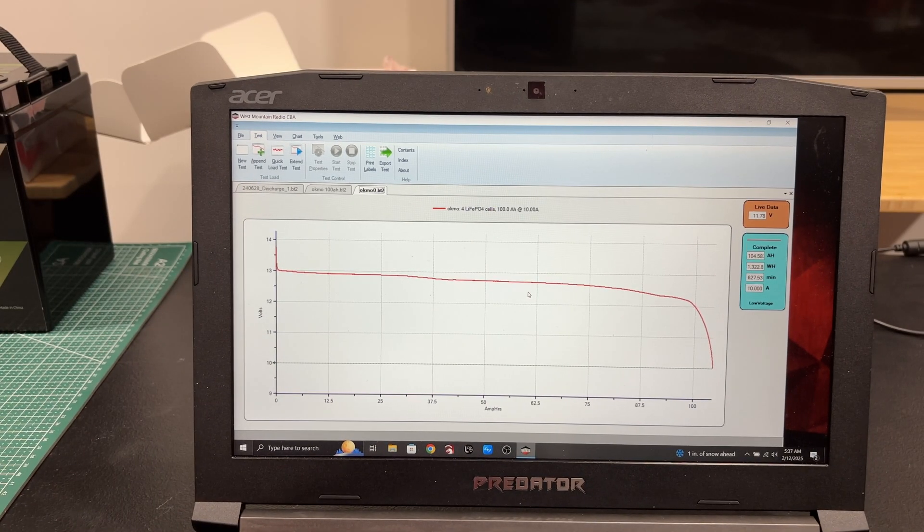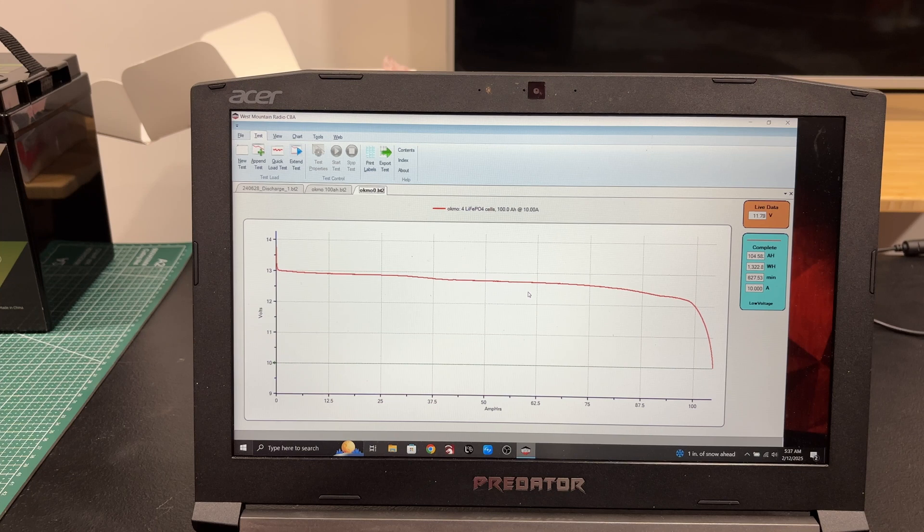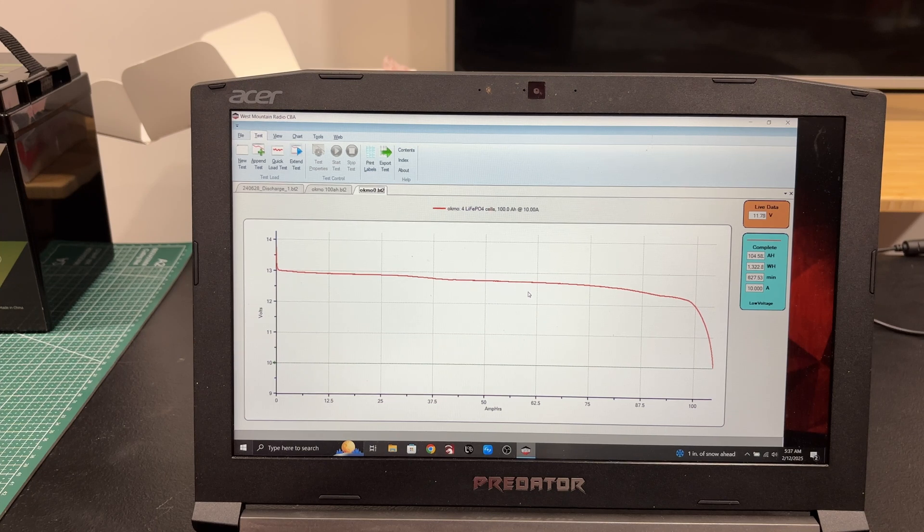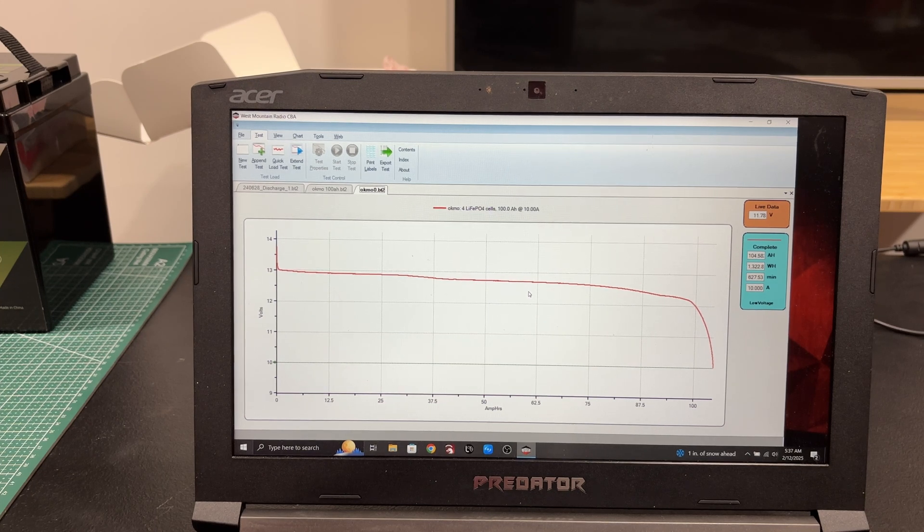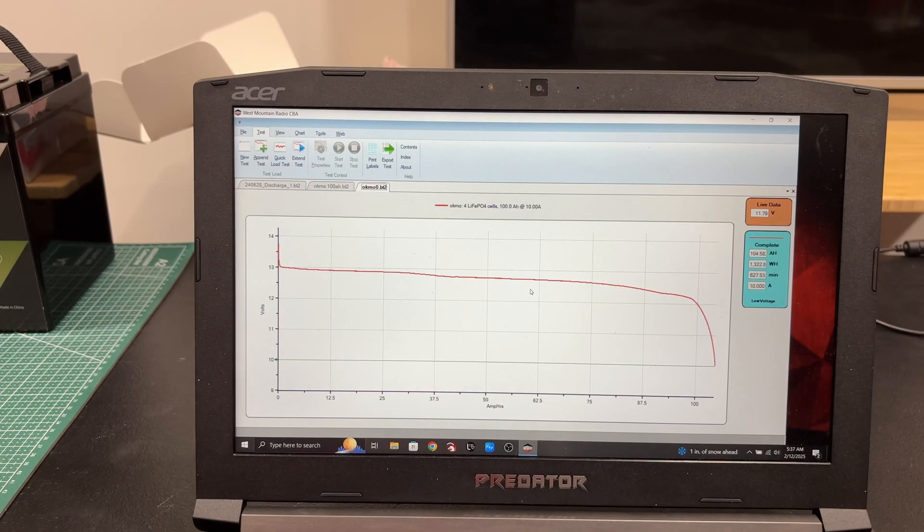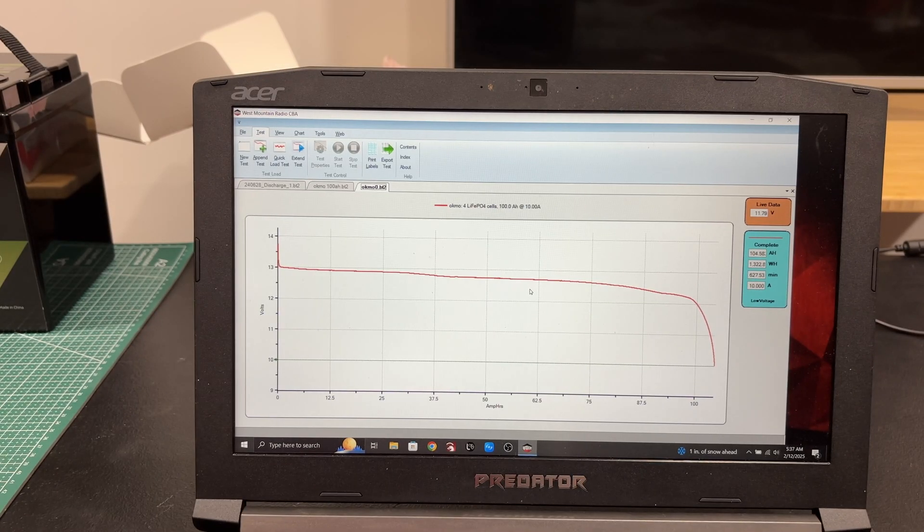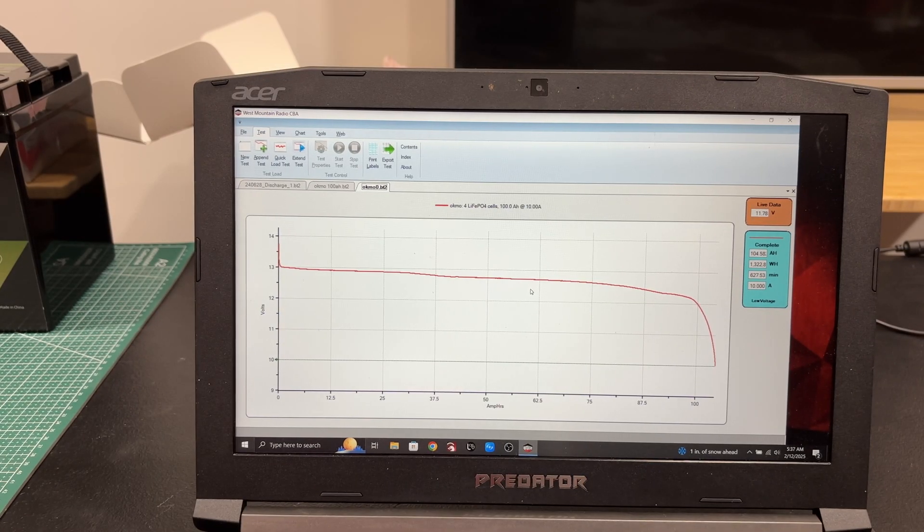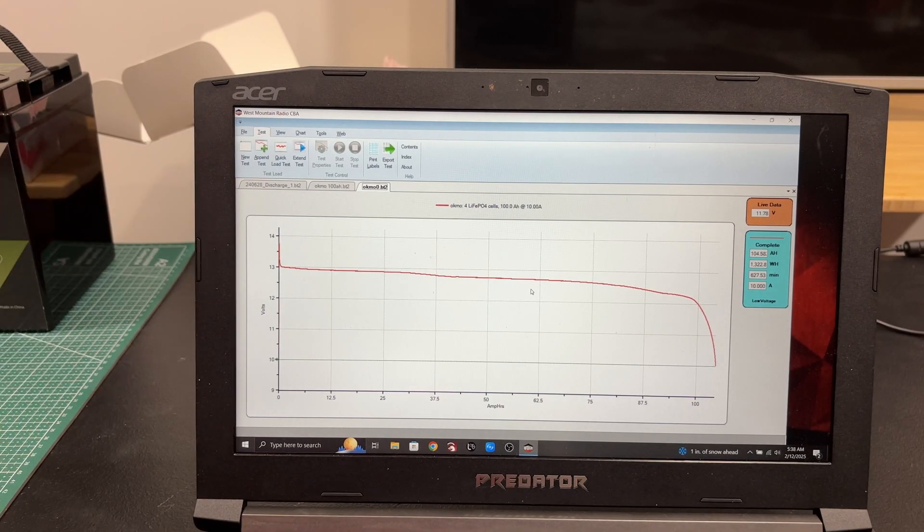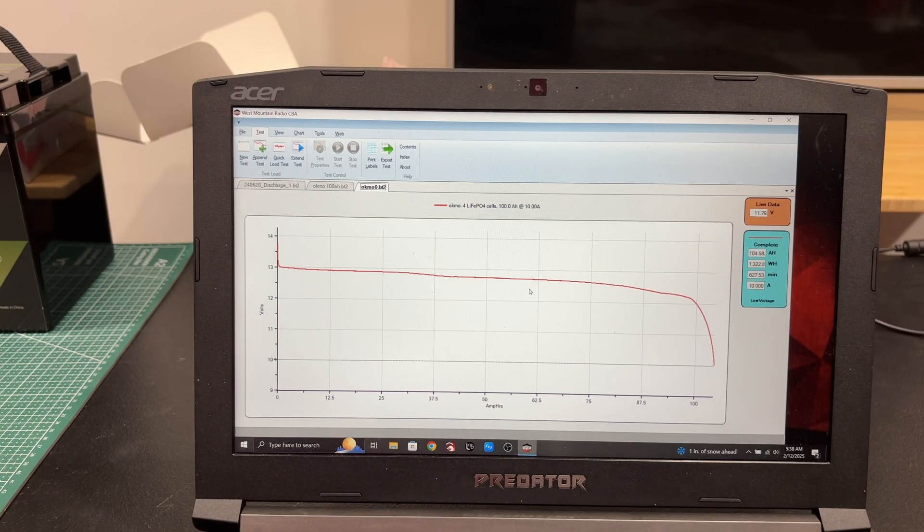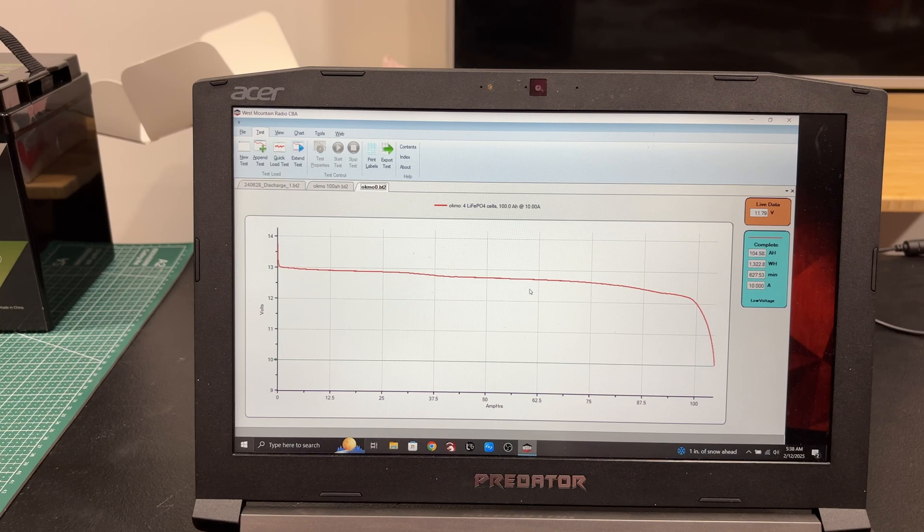Which is 1322.8 watt hours, so it over-performed a little, which is always nice. It took 10 hours 27 minutes to run the test drawing down at 10 amps. Yeah, I mean it's pretty good.